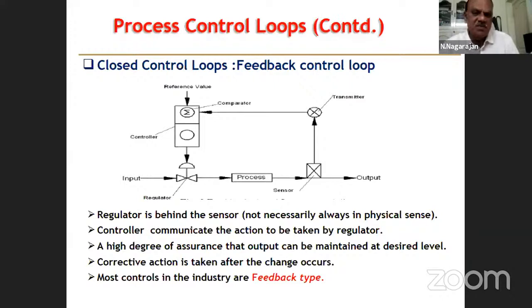So this is a feedback control loop. Feedback means we have the process here, we measure the output variable, its value here, that is a sensor, a transmitter which converts the measured variable value into a signal which goes to the comparator. The comparator compares the measured variable and the set point here. Reference value is nothing but a set point. Then the control action is decided here. That will either open or close the valve.